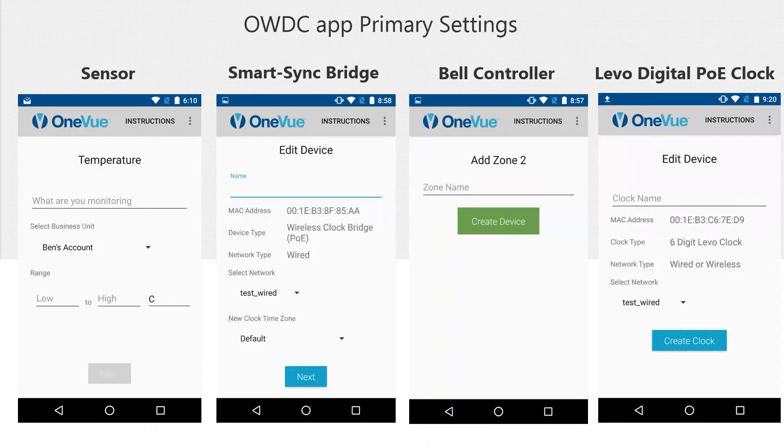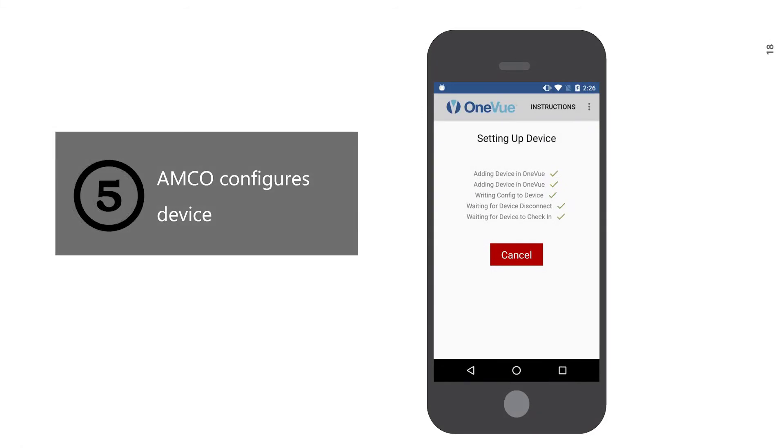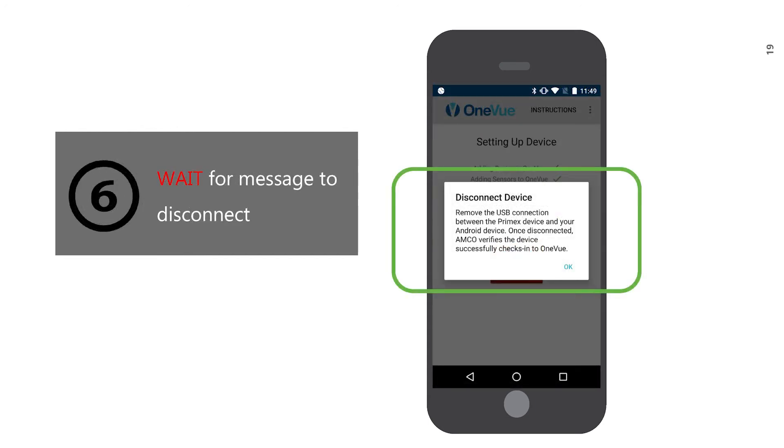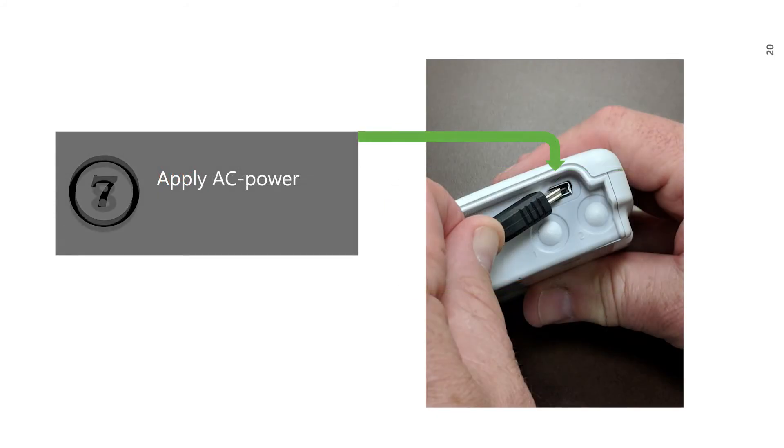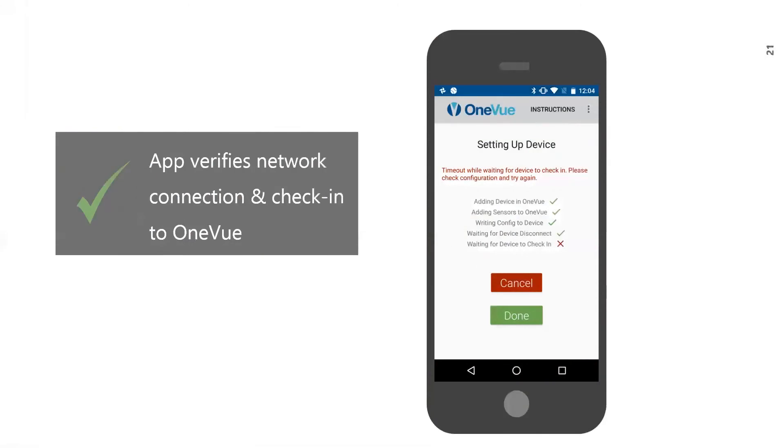For all devices, when a non-DHCP network is selected, you must provide the device's static IP address. The app is intuitive, providing a step-by-step experience to easily configure a PrimeX device on-site during installation or service. The app then configures the device and displays the status of the configuration. Do not disconnect power until the app tells you. You will see a message to disconnect the PrimeX device from the Android device — do so at that time. Then connect AC or battery power to the PrimeX device. The app then verifies the device checked into OneVue successfully. Select Done — configuration is then complete, and you can configure additional devices as needed.